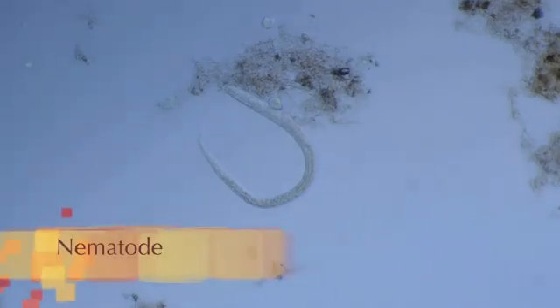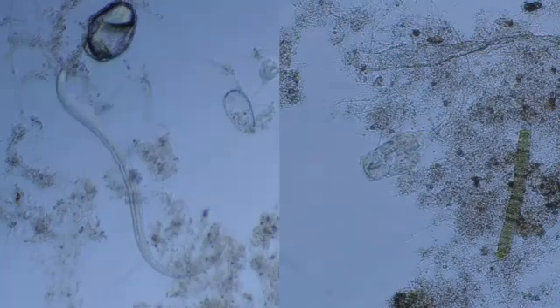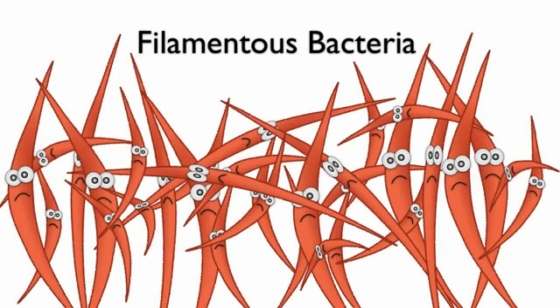Our worm friends, the nematodes - these tiny worms can be active or just swimming lazily around and can also be an indicator of certain conditions. Both nematodes and rotifers can be indicative of an older bacterial biomass and in wastewater are indicative of a higher degree of purification or seeding from an attached growth system.